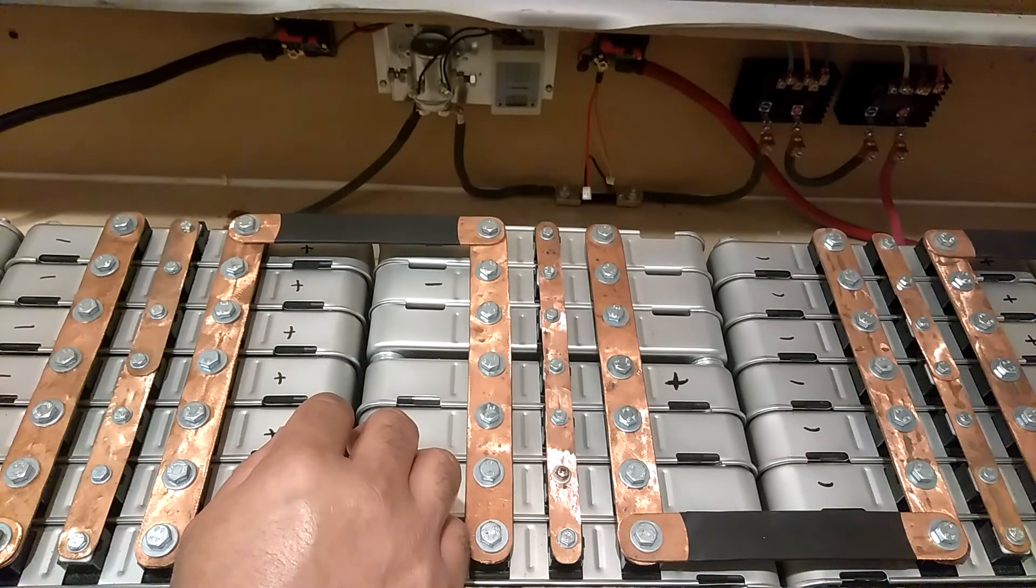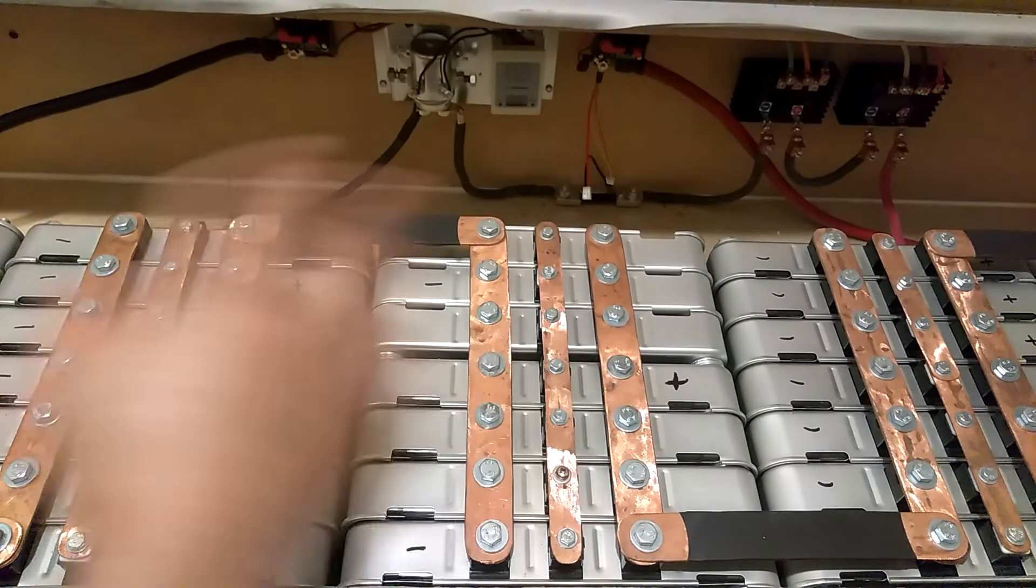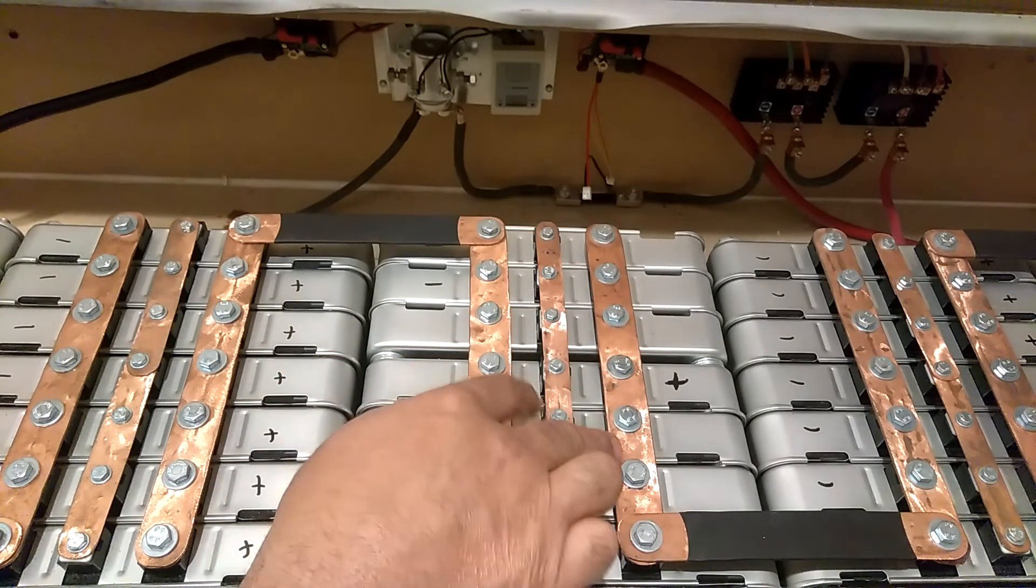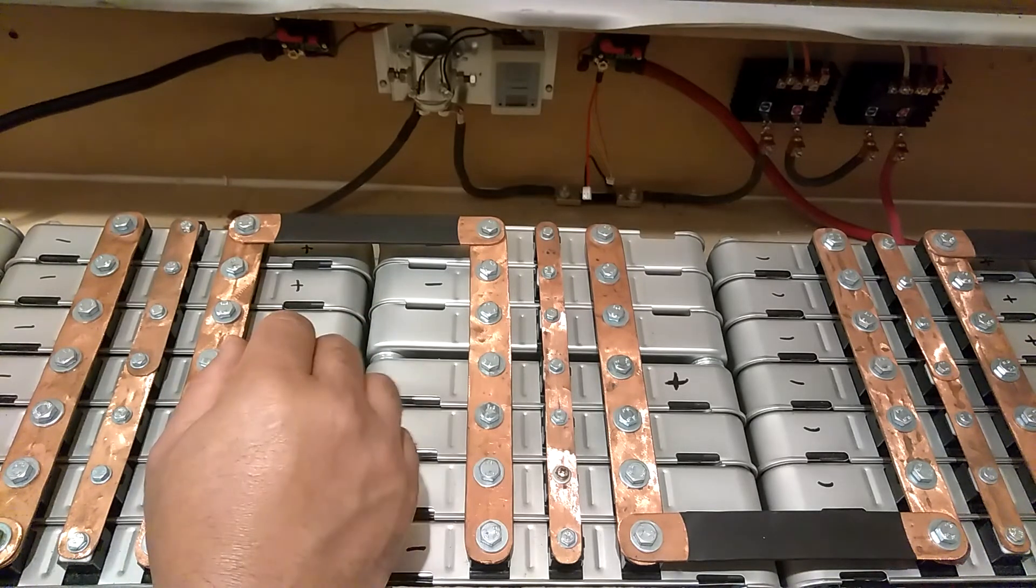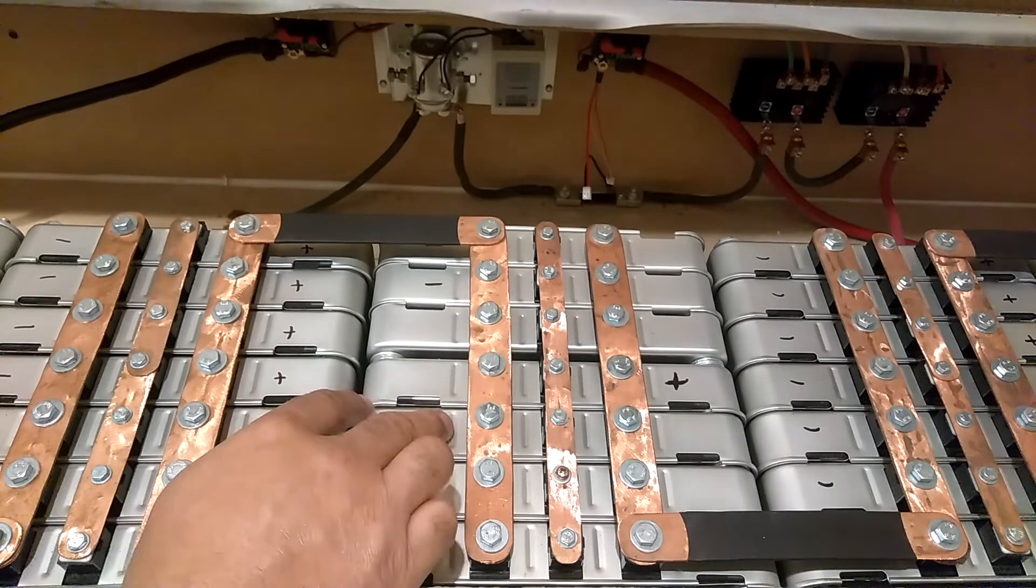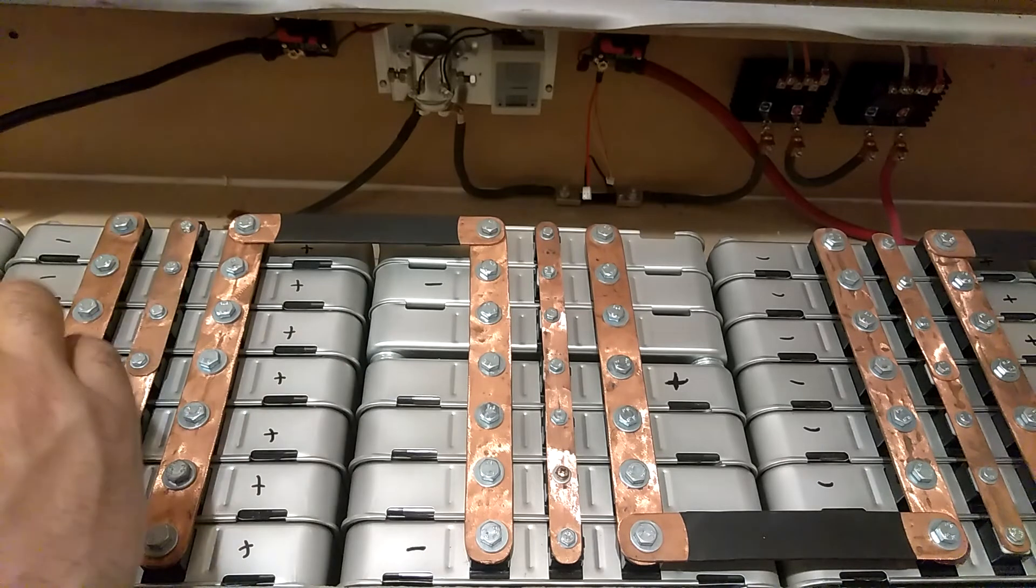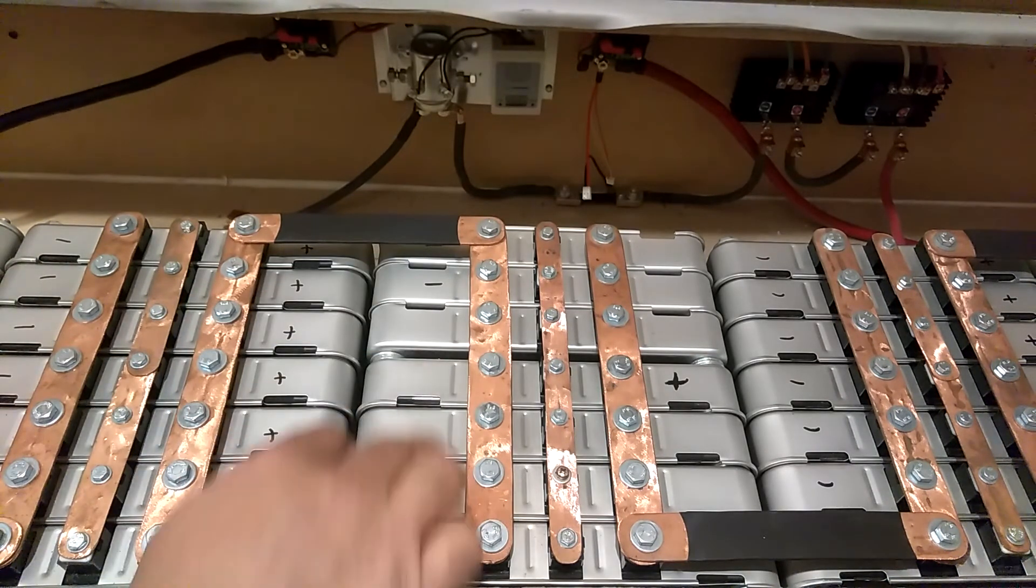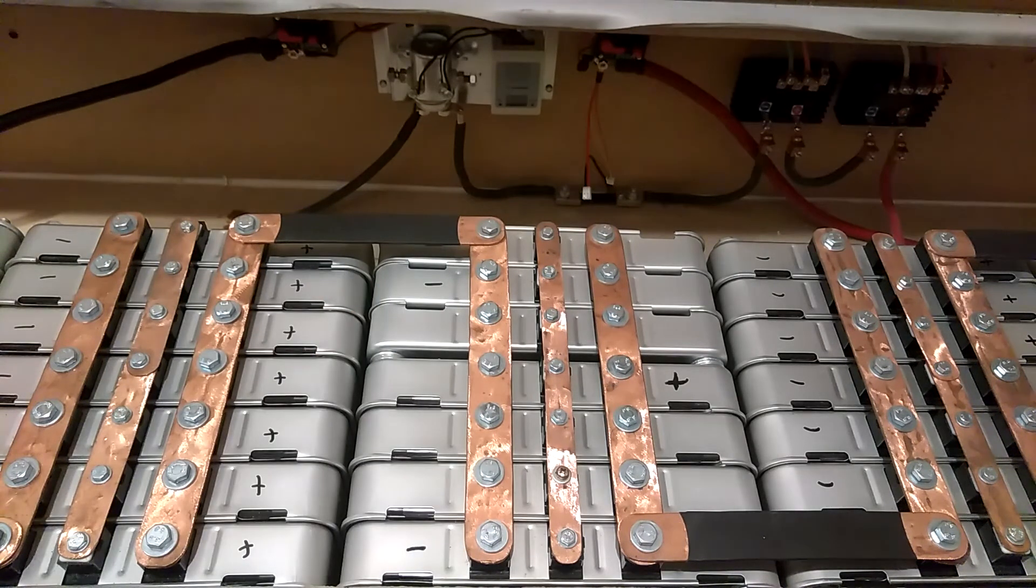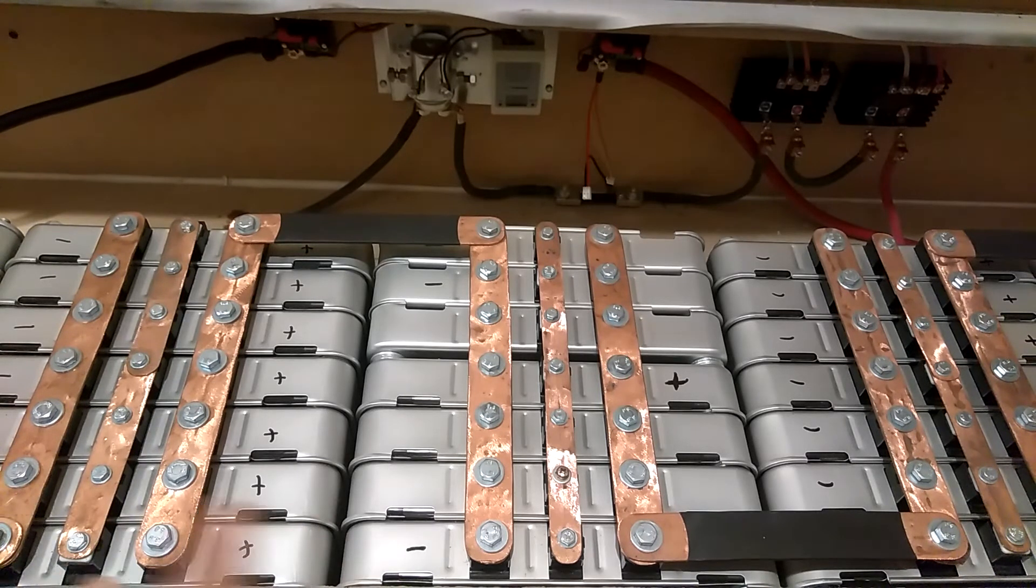And what I normally do is probably about once a month, sometimes once every three weeks, I take these, I shut the whole system down, switch over to the grid, I pull all of these bus bars off of here, I let the batteries sit for a couple of hours, and then I check them to make sure I don't have any in this pack here that's bad or reading low. And I never had any. All of these batteries in parallel normally stays equal, so that's why I think my pack stays so equalized.